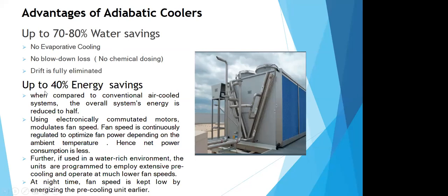And we talk about 40% of energy savings. How do we incur 40% energy savings? When we move from an air-cooled system to a water-cooled system, we know that the power consumption drops by almost 50%, from 1.2 kW per ton to around 0.6 kW per ton. And with the help of these electronic EC fans, one can control the speed of the fan depending upon the load, and they optimize the power consumption depending on the ambient temperature. So the net power consumption on an annual basis is reduced considerably.